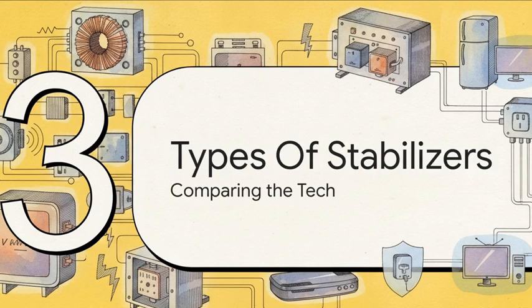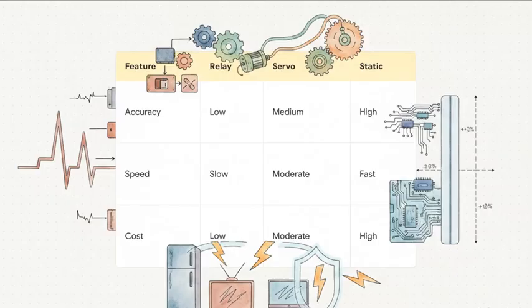Okay, moving right along to section 3, types of voltage stabilizers. Let's compare the actual tech on the market. There are 3 main heavyweights in the industry. First up is the relay stabilizer, which is low cost and simple, using stepwise adjustment. Then we have the servo stabilizer. This one actually utilizes little motors for moderate, continuous adjustment and can handle much higher capacities. And finally, the static stabilizer. This is fully electronic, boasting incredibly high precision. We're talking staying within plus or minus 1% accuracy, and it handles dynamic changes instantaneously, with absolutely zero mechanical parts.